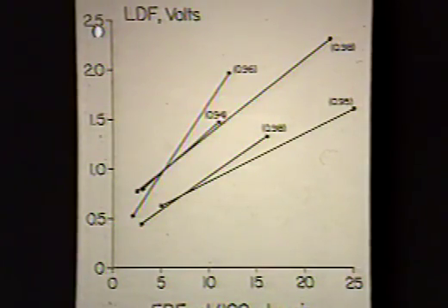The good news is that these are the correlation coefficients, very high correlation coefficient in each case. A linear relationship between the laser Doppler output and the plethysmographic output. The bad news, of course, as you can see, and has been alluded to already this morning, is that there is no singular relationship. Instead, each study tended to define a different relationship between these 2 measures.